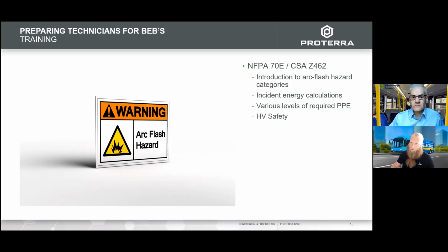Now, the differences between those also means that there's a different calorie rating per arc flash suit. So you may have an 8 cal, 12 cal, 15 cal, 40 cal, and so on that come into play here. So understanding that and how that also plays into the incident energy calculations, not that a technician needs to do any of these calculations, but more being able to read what those incident energy calculations are, and then appropriately using the right arc flash hazard category associated with those calculations. So again, looking at that as well as the various levels of PPE required and the high voltage safety associated.